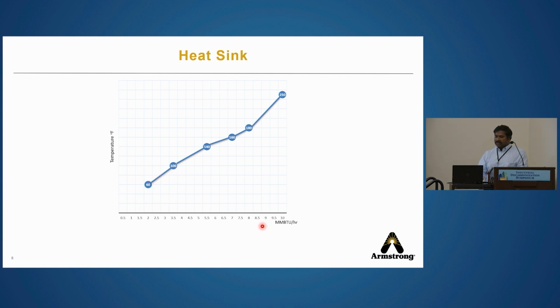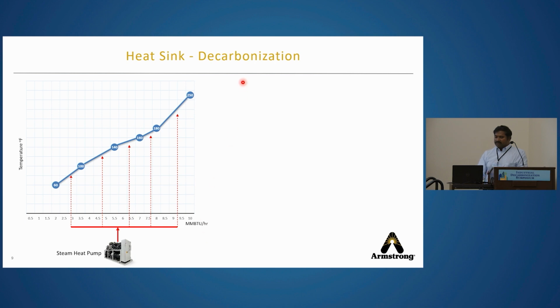So on the x-axis, you can see the heating capacities in million BTUs, and temperature on the y-axis. This could be process A, where it requires heating from 60 to 100, process B, etc. So you plot all the heating requirements in a chart, and currently all this heating could be done with the help of a steam boiler, and the steam meets all the heating needs in the facility. Because of decarbonization, most customers jump right into a steam heat pump, utilizing their existing steam network. But we just saw that having a steam heat pump to generate a process at 140 or 100 degrees Fahrenheit is not that efficient.